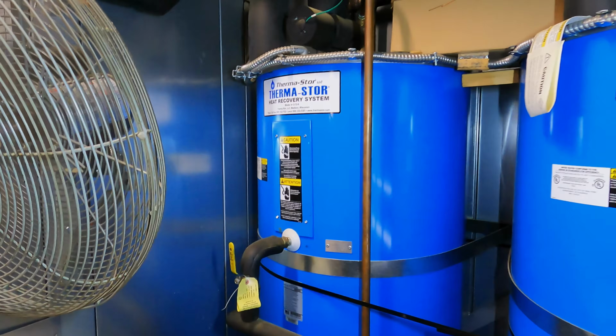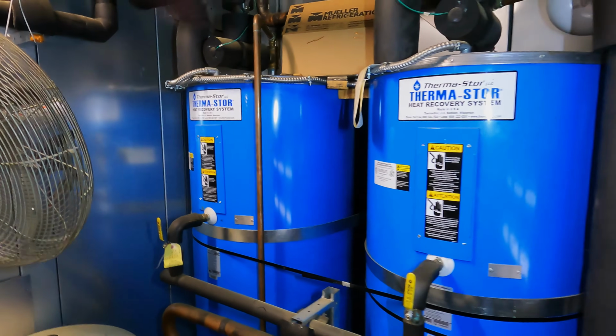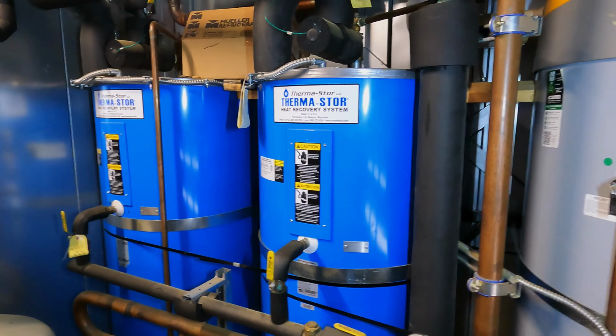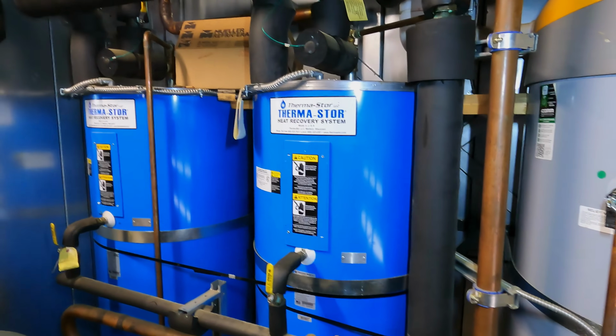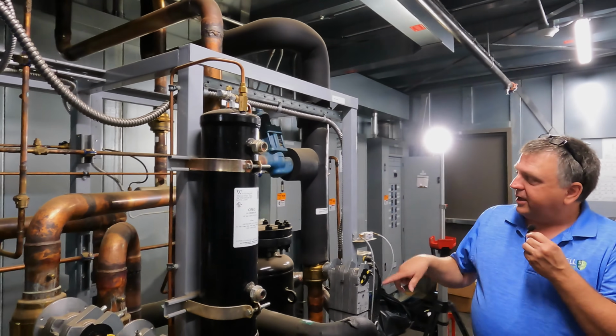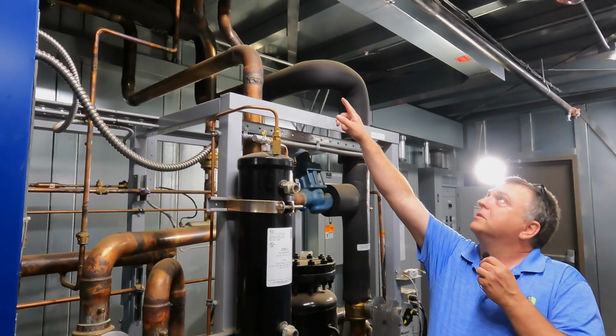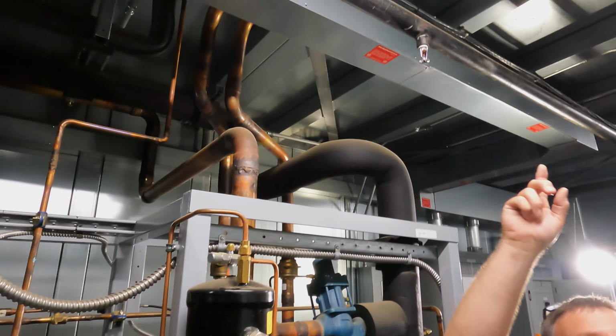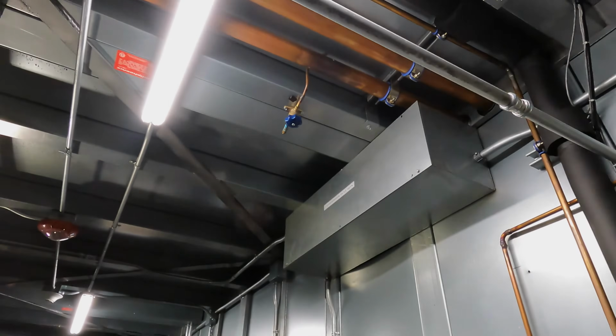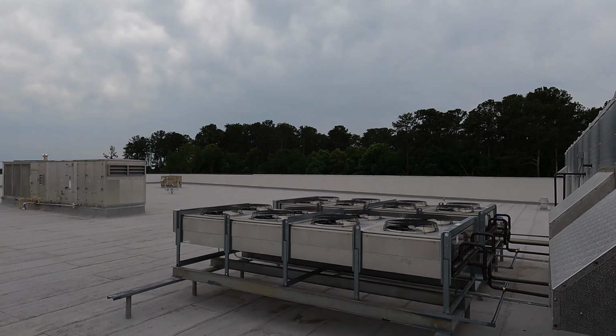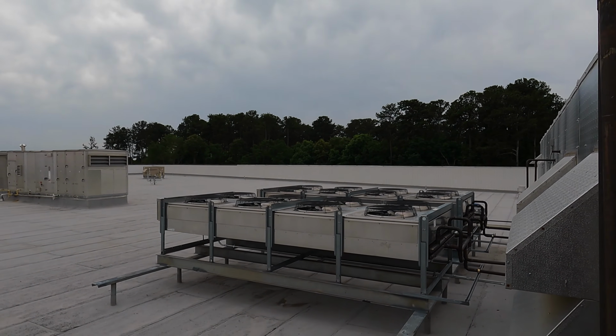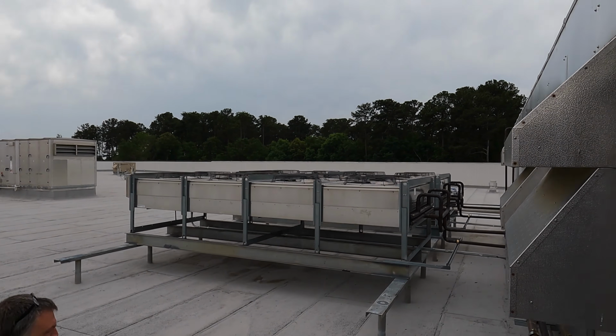We have discharge gas. We have some reclaim tanks, so we're going to use that extra heat to heat the hot water. It's free heat, right? We want to do that. Once it's gone through our heat reclaim, it's going to go to our piping and our outside condensers. And then these are our condensers for that Rack 2 449A. There are not any CO2 condensers out here.